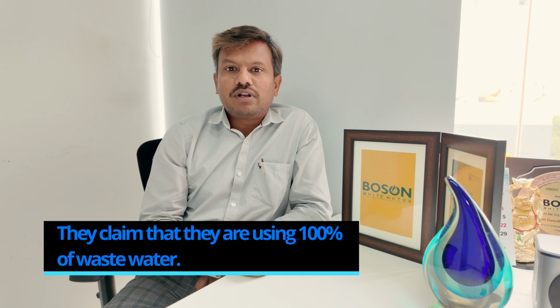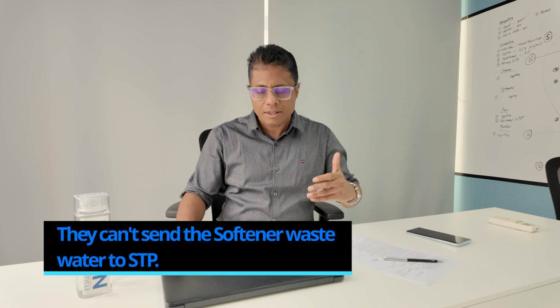That's the ground reality. When IT parks and malls pass their STP treated water via softener and then take it to the cooling tower, they only reduce the hardness of the water and not the total dissolved salts. Any softener, when it reduces hardness, requires regeneration. For example, for every 1 lakh liters of soft water generated, they end up using 200 kgs of salt. Imagine a small mall of 5 to 6 lakh square feet using 6 to 7 tons of salt. This entire salt solution goes as waste, and they can't send it back to the STP.